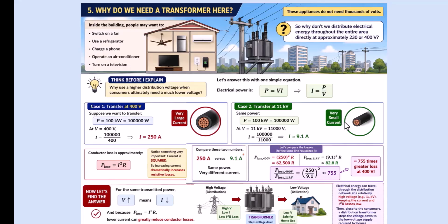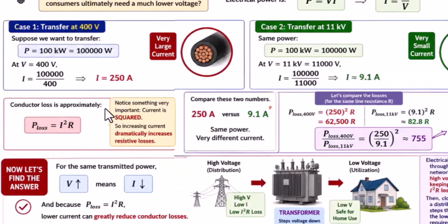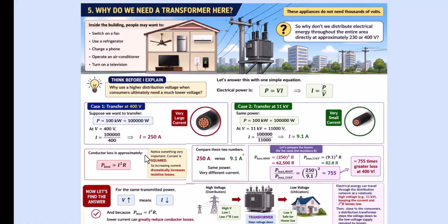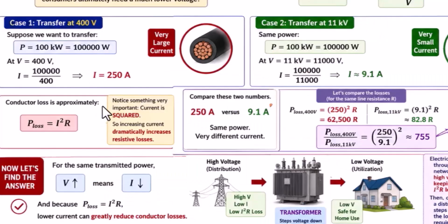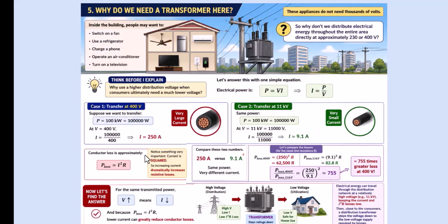Stop here. Compare these two numbers, 250 ampere and 9.1 ampere. Same power, very different current. Why does that matter? Because conductor loss is approximately P_loss = I²R. Notice something very important, current is squared. So increasing current dramatically increases resistive losses. Now let's find the answer. For the same transmitted power, if V increases, I decreases. And because P_loss = I²R, lower current can greatly reduce conductor losses. That is one major reason electrical energy is distributed at higher voltage.